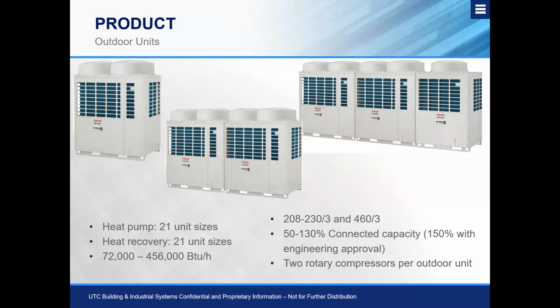And of course, as we go above, let's say 7 tons on a 6-ton system, we start looking at 115% capacity. What we're talking about in percentage is the amount of indoor units compared to the total tonnage of the outdoor unit. So 50%, or half of the tonnage, is our minimum, up to 150% connected capacity with factory approval. But again, when we look at our load balances throughout the day, especially when we're going above 100% connected capacity, make sure that we're not shooting ourselves in the foot and we don't have enough capacity for the worst condition that we would have in the hot portfolio.